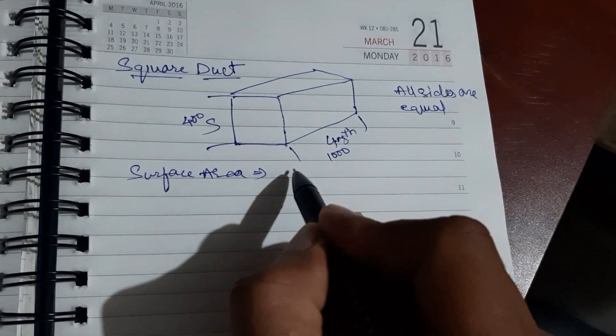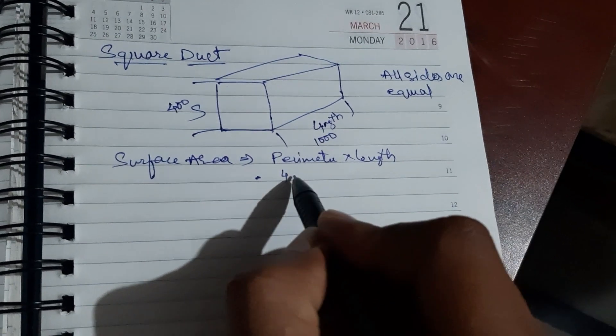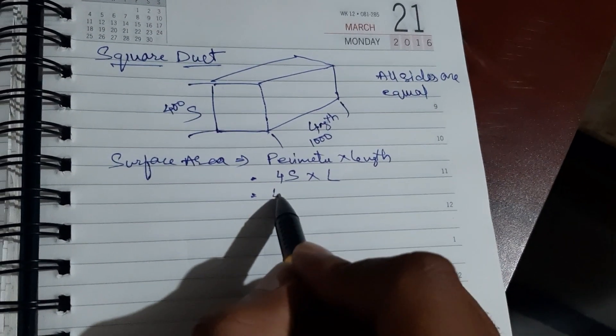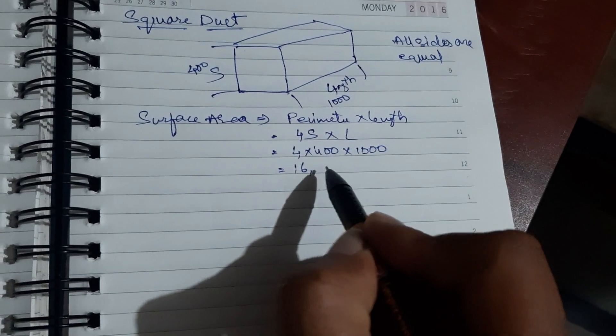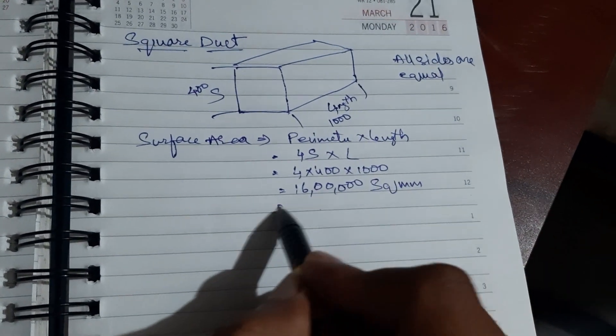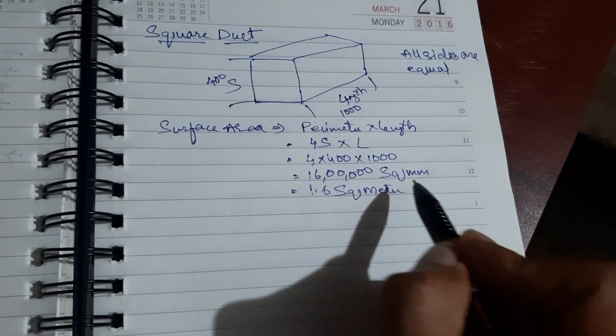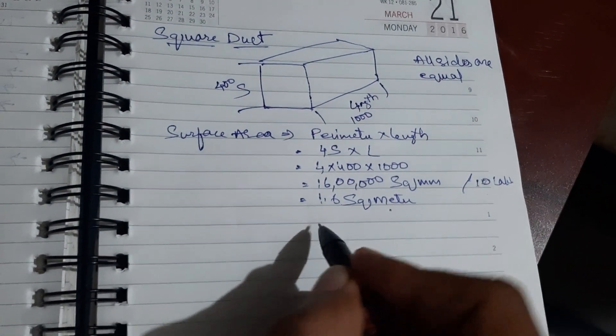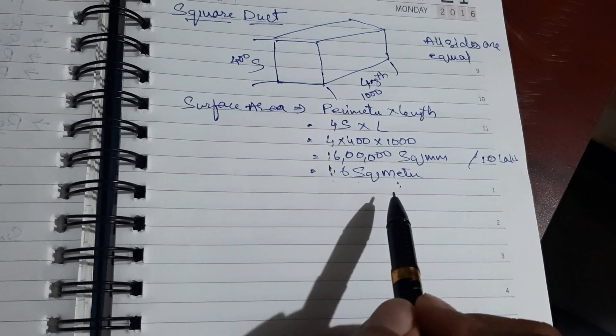Surface area equals perimeter into length. The perimeter of a square is 4s, so: 4 × 400 × 1000 = 1,600,000 square mm. To convert to square meters, divide by 1,000,000. We get 1.6 square meters as the surface area of the square duct.